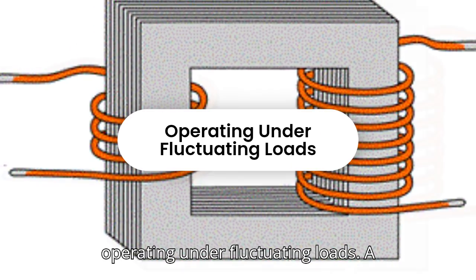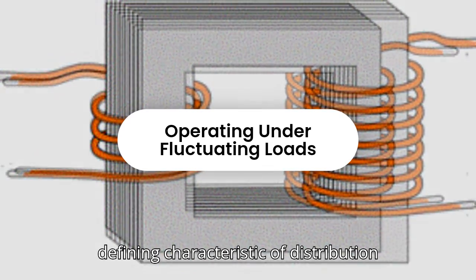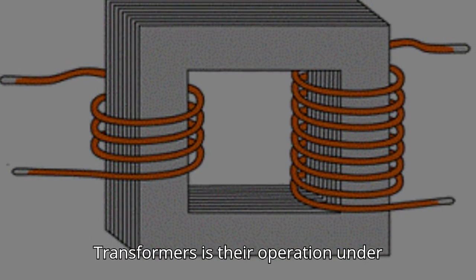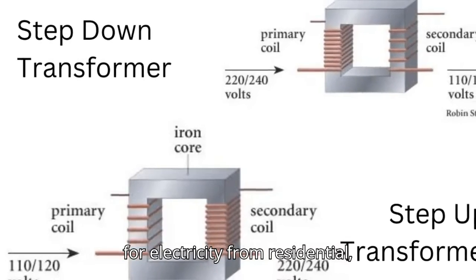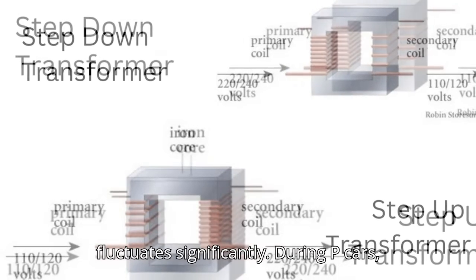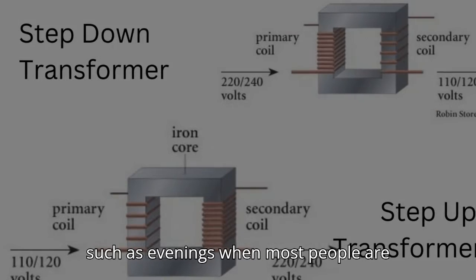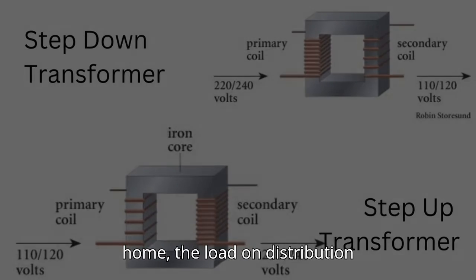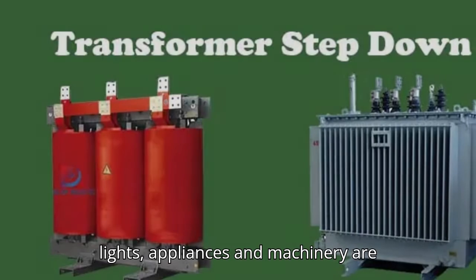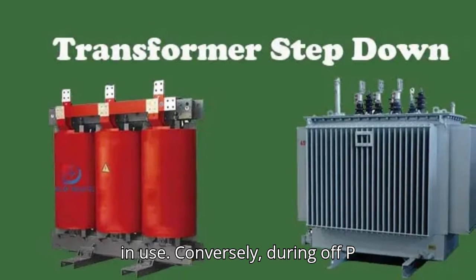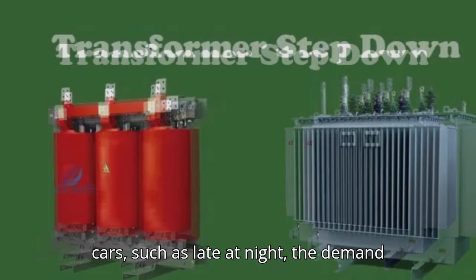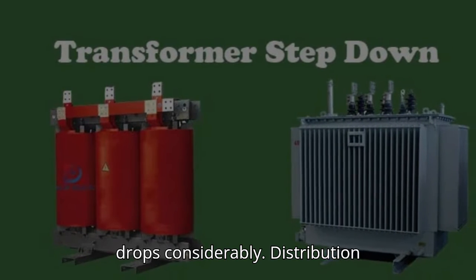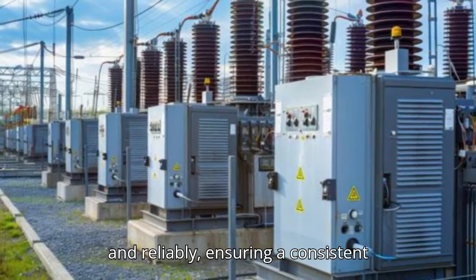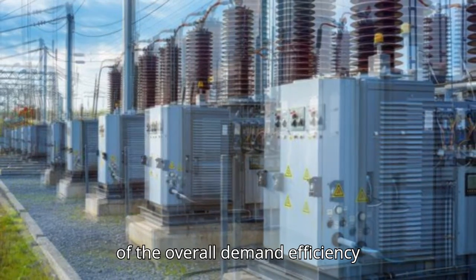Operating under fluctuating loads. A defining characteristic of distribution transformers is their operation under constantly varying load conditions. Throughout the day and night, the demand for electricity from residential, commercial, and industrial consumers fluctuates significantly. During peak hours, such as evenings when most people are home, the load on distribution transformers increases substantially as lights, appliances, and machinery are in use. Conversely, during off-peak hours, such as late at night, the demand drops considerably. Distribution transformers must be designed to handle these dynamic load changes efficiently and reliably, ensuring a consistent supply of power to consumers regardless of the overall demand.